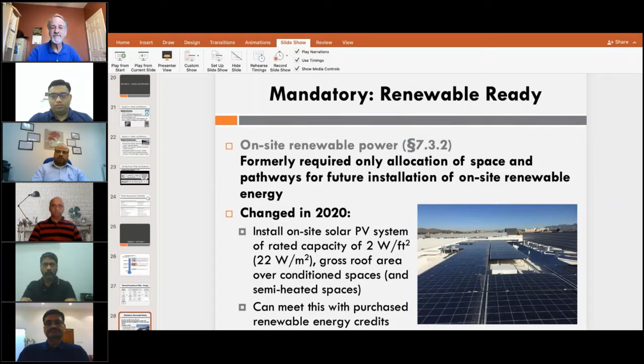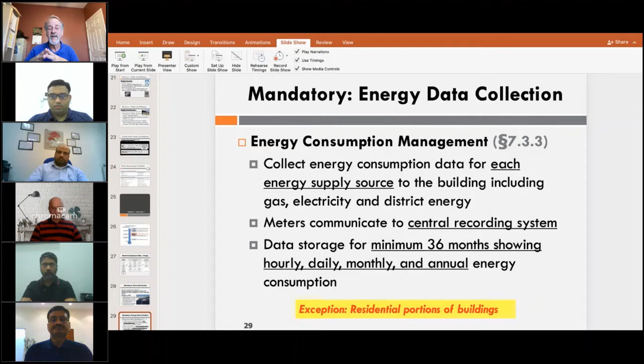Those meters communicate back to a central recording system, and you store the data for a minimum of 3 years. So you've got hourly, daily, monthly, annual energy consumption. You can go through and analyze that and get information from there. Now, again, what is the purpose of this? It tells you where your energy is going. So looking at the lower left-hand side right here, again, these are all lumped together. So it's not requiring energy measurement of specific pieces of equipment. I've been trying to push for that for a number of years, but we just can't quite get that worked out.